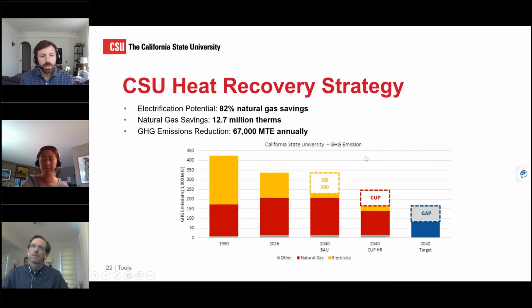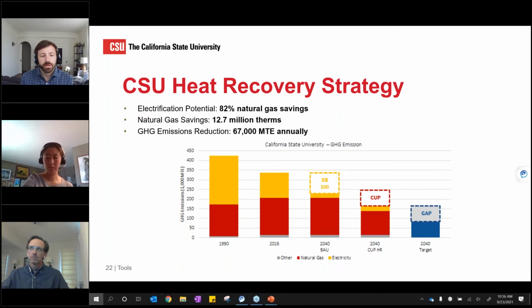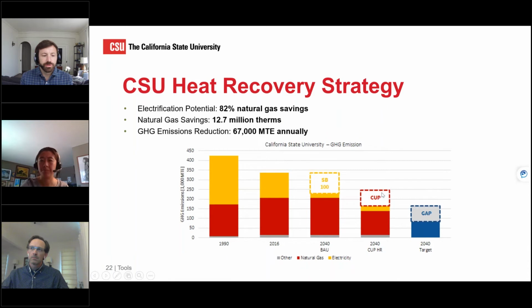Looking across all 23 campuses at a system-wide level, we found that with heat recovery, thermal energy storage, and free cooling, we can reduce central plant natural gas use by 82%, accounting for a 12.7 million therm reduction, and reduce annual emissions by 67,000 metric tons of CO2 equivalent, taking a significant chunk out of CSU's emissions profile to meet their 2040 target.